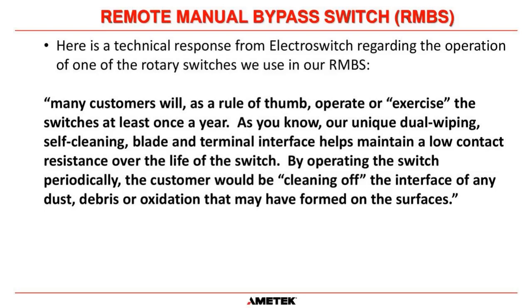You could, in theory, when you go from the normal position to the bypass position, because that corrosion caused by the H2S has not been cleaned off by regular exercising of the switch, there is a possibility that when you move that switch, the contact from the make before break doesn't actually make, and it could, in theory, drop the load. So the manufacturer does recommend that you do exercise your switch on a periodic basis.